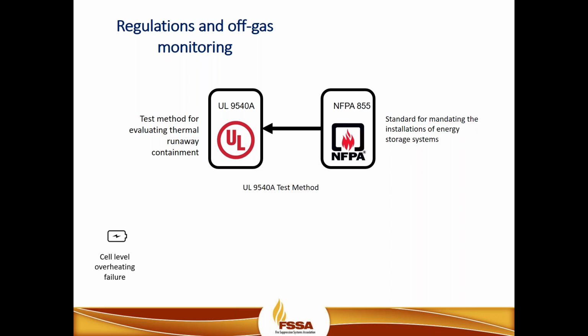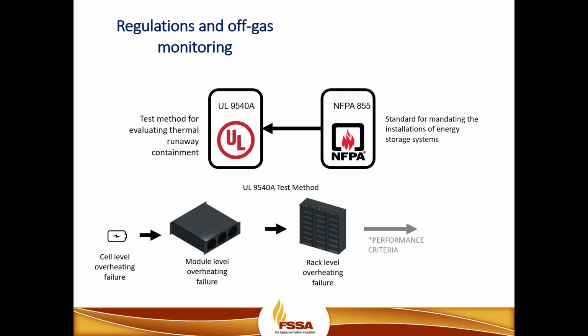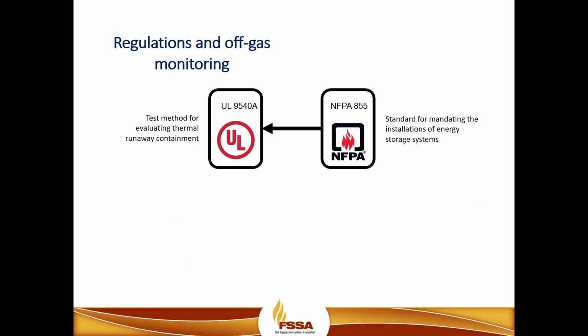So if you look at the test standard for UL 9540A for lithium-ion batteries, of course, it's a test method that tests all lithium-ion batteries, and it really is pushing the batteries to their limits to a failure state. So initially it looks at the cell level and using an overheating and overcharging abuse factor reaching at the cell level a failure rate, documents that at the cell level, at the module level, at the rack level, and even at the system level. So it's documenting how the batteries responded to the overheating and overcharging event, and of course the risk associated with that.